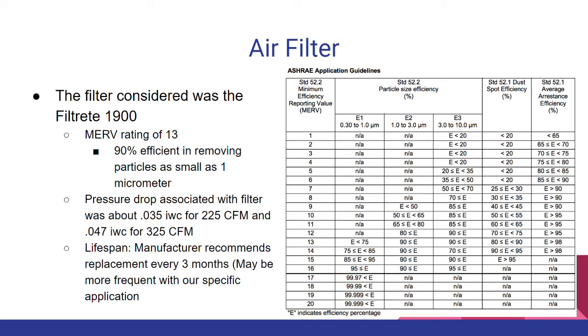The manufacturer recommends replacing this filter every 3 months, but it may be more frequent within our application as it could possibly restrict airflow. The image to the right is ASHRAE's air filter application guidelines that show the MERV ratings and the corresponding efficiency of removing particles of different diameters.